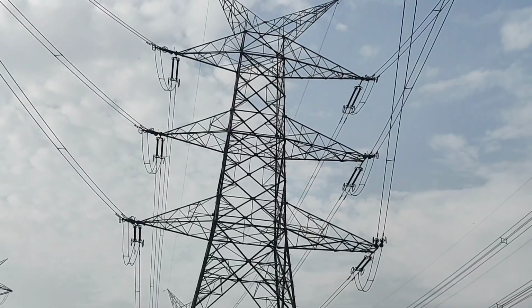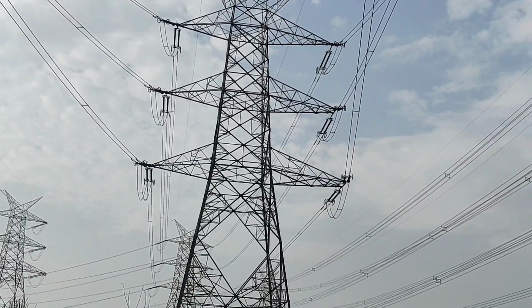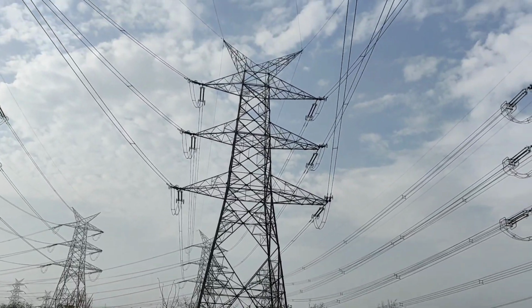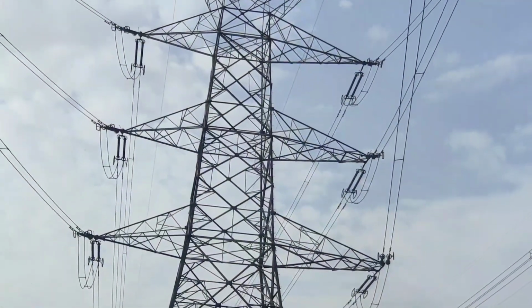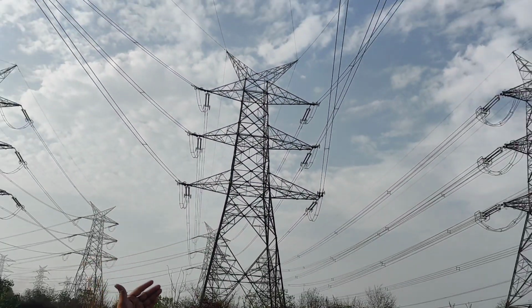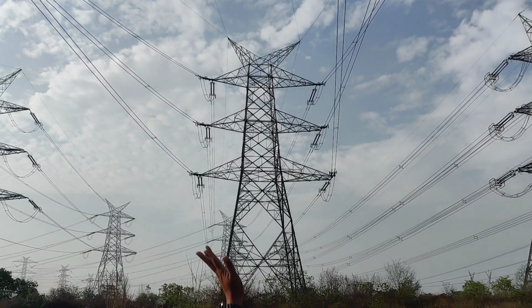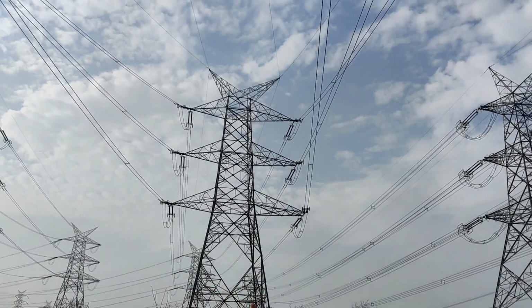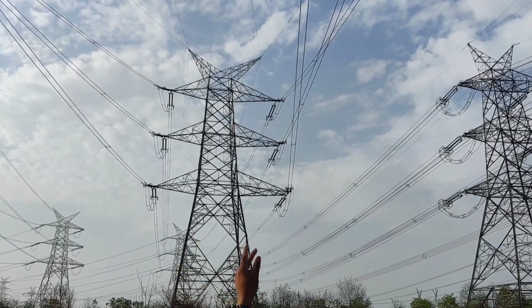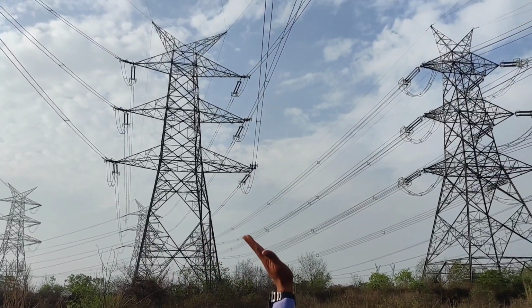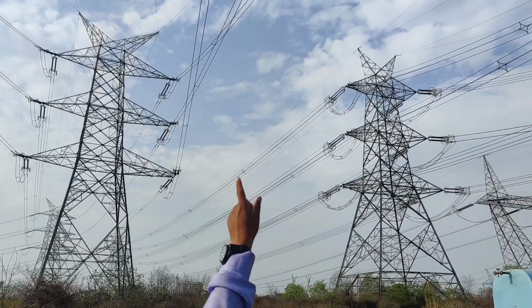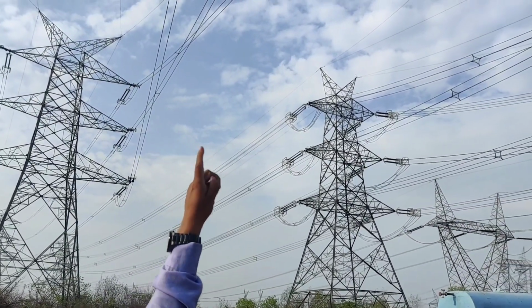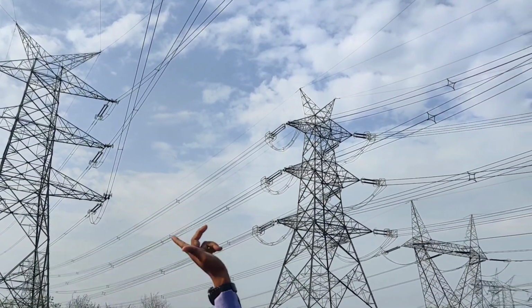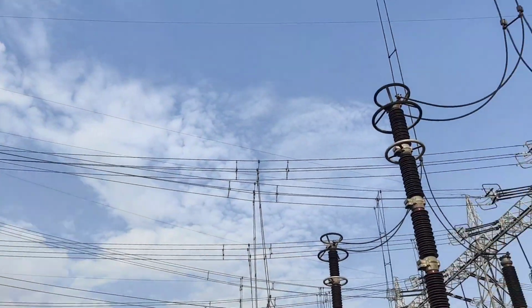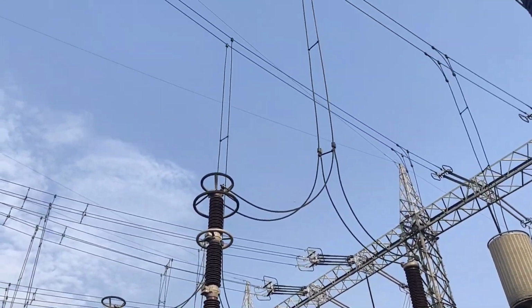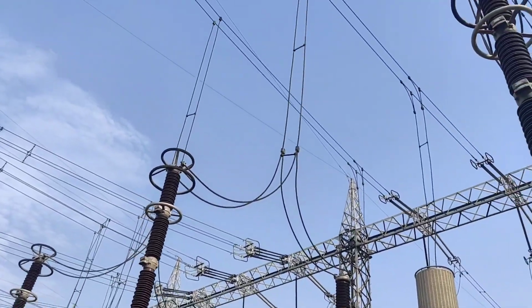Basically, if you see, there are three conductors on the right hand side and three conductors on the left hand side. That means this is a double circuit tower, and if you focus on a single set of three conductors, then the right hand side is one transmission line. Those three conductors are for R phase, Y phase, B phase, coming from that side, and it is connecting firstly to this equipment.